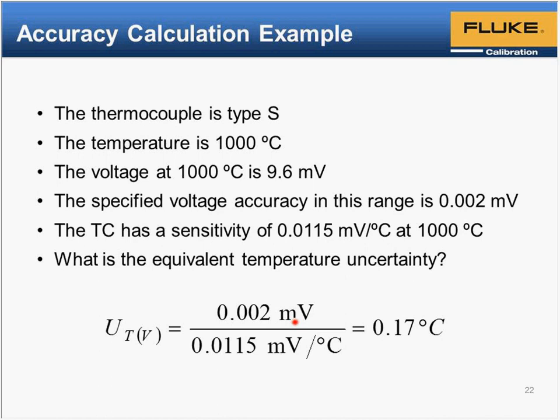So to divide that by the sensitivity of the Type S thermocouple, we look at the sensitivity at 1000 degrees C, which is 0.0115 millivolts. So 12 microvolts per degree. That's why you have to have a pretty good meter to be able to measure these successfully, and a meter that's able to measure with low voltage noise is able to get a stable reading. It's math, and that is a 0.17 degrees C equivalent.